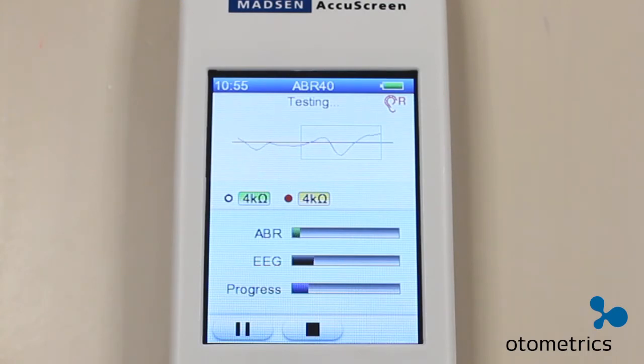The blue bar, progress, indicates the overall progress of the measurement, but it is not a measurement of time. Instead, it will progress rapidly if a high quality of data, that is, with low noise, is collected. It will progress very slowly if a low quality of data, that is, with a lot of noise, is collected. You can view the ABR test as a race between the green and the blue bar. If the green ABR bar reaches its endpoint before the progress bar, a pass will be issued. Otherwise, a refer will be issued.